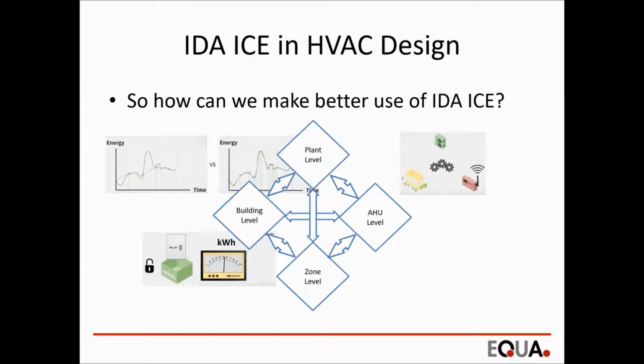So you could send a signal from the zone to the plant, then take an action signal back, a control signal from the plant to the zone. You're able to communicate throughout these levels in the background in a very easy way. We're going to see how this helps not only design better control systems and strategies, but also enables much faster simulation time, because you reduce redundancy -- you reduce the need to model several controllers in every zone when you have one controller communicating to all zones.